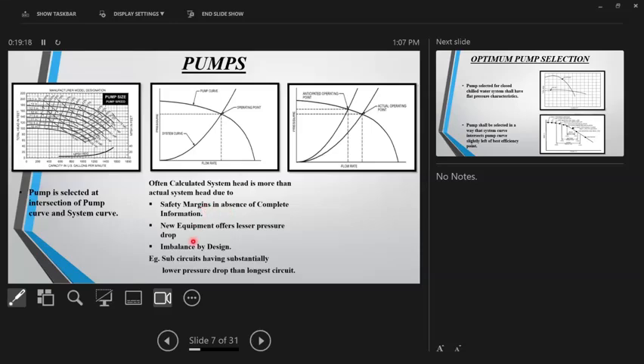Then, when you do the pump head calculation, you would select the pressure drop when the equipment is dirty, right? But when the equipment is new, it offers very little pressure drop. The example is a strainer. You would select the pressure drop in a kind of dirty condition, but when the systems are new, the strainers are going to be clean. And imbalance by design, that's a reality of life, that some circuits will be substantially longer than others. This is also unavoidable.